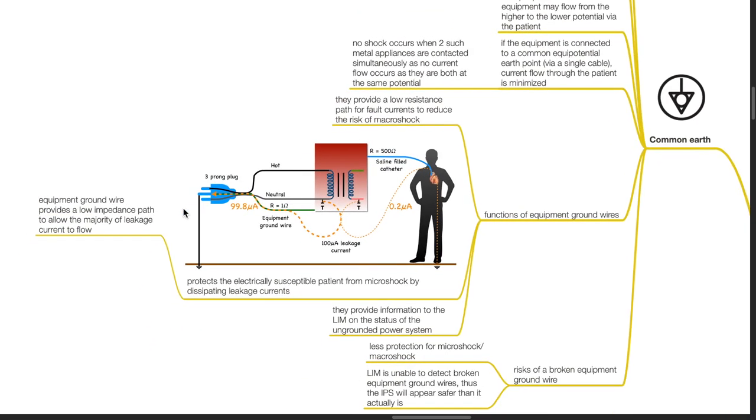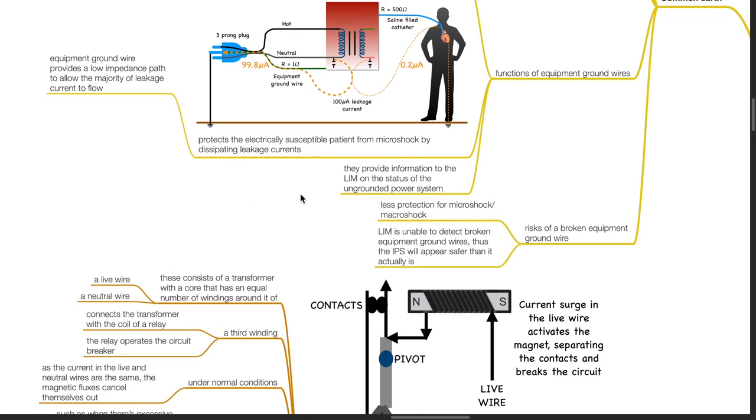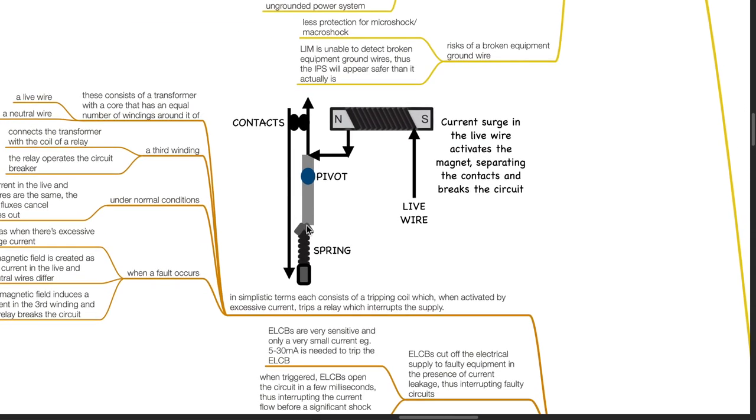Functions of equipment ground wires: They provide a low resistance path for fault currents to reduce the risk of macroshock. They protect the electrically susceptible patient from microshock by dissipating leakage currents. Equipment ground wire provides a low impedance path to allow the majority of leakage current to flow. They provide information to the LIM on the status of the ungrounded power system. Risk of a broken equipment ground wire: There will be less protection for micro and macroshock. LIM is unable to detect broken equipment ground wires, thus the IPS will appear safer than it actually is.